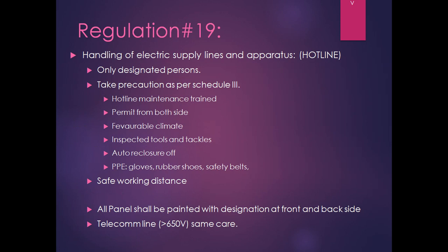Regulation 19, again it's a very important regulation. This regulation is for handling of electrical supply lines and apparatus, or sometimes we call it hotline. Only designated persons shall be working on the electric supply lines and apparatus plants. They should take precaution as per schedule 3. That means they should be hotline trained persons. They should have permit from both sides of the lines. Somebody calls it line clearance permits.